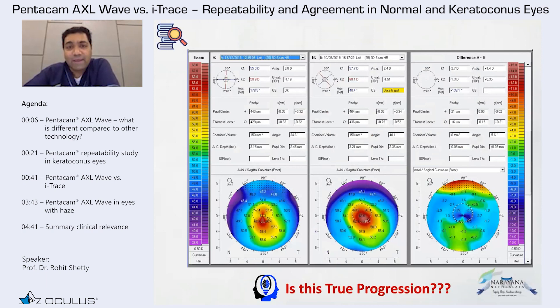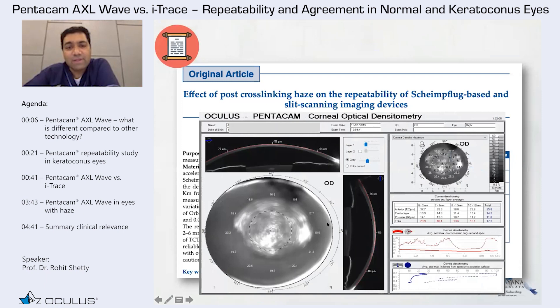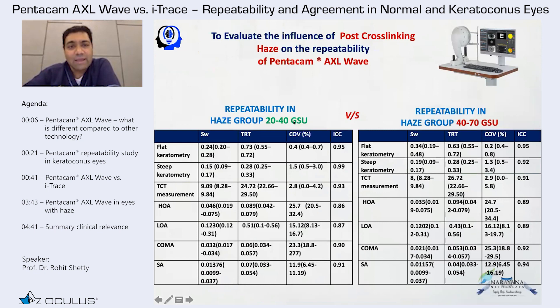The effect of haze is something we have worked on and published — how haze impacts measurements. This is a very useful and underutilized part of Pentacam, especially in cross-linking. We are working on AI models for every level of haze and its impact. We found that different grayscale units of haze have different repeatability, meaning your repeatability changes with the level of haze. The software needs to incorporate this in the future, as it will have a huge impact on cross-linking outcomes.